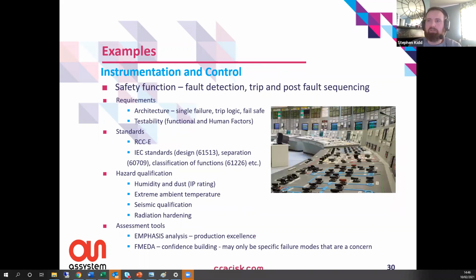And finally, just quickly run through an instrumentation and control example. So again, very similar. If we look at fault detection, trip and post-trip fault sequencing, there may be architecture requirements. So a specific architecture that we're looking to implement, depending on the class of the system. If it's class 1, as I mentioned before, it might have several layers of redundancy. We might need to build in testability functionality to be able to maintain and monitor the EQ through life. There are lots of standards that might be specified dealing with lots of different aspects of I&C, like design, separation, classification of functions. Depending on the class of the system, there are different requirements and different qualification requirements.